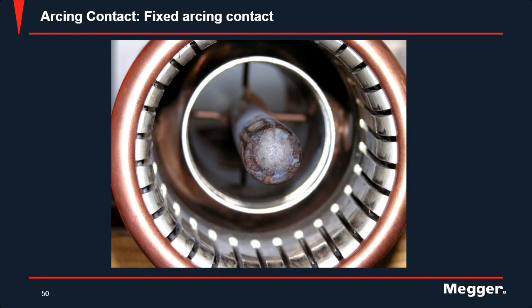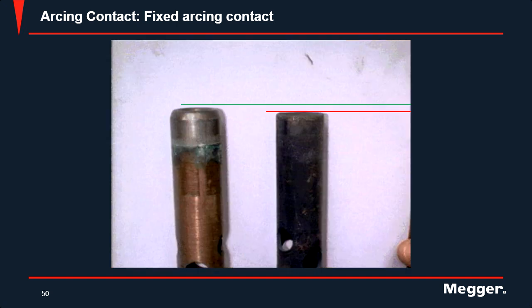So here's a picture of the arcing contact, the stationary one inside the interrupter, as well as a good arcing contact versus one that's been heavily corroded based off arcing or short circuit faults.